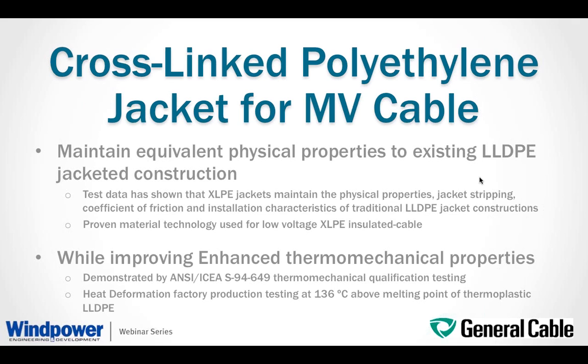So here we'll talk about the cross-linked polyethylene jacket, and the additional benefit that, in addition to maintaining equivalent physical properties to the existing LLDPE jacket construction, it provides enhanced thermomechanical properties, reduced copper in the concentric neutral, and allows for cooler operation and optimized efficiency with lower line losses.